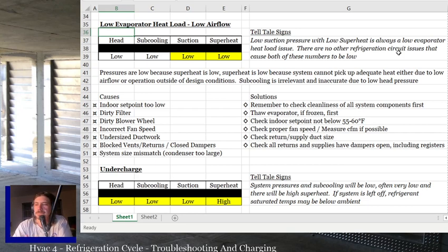Now, I will say this, though. My experience has been, and this isn't all the time, but it's most of the time, if you've got low evaporator heat load because of a dirty filter, or a damper's closed that shouldn't be closed, or whatever the case may be, and it's frozen up when you get there, you thaw it out and throw a new filter in. Don't necessarily call it good, because my experience has been that if the system actually freezes up into an entire block of ice, it's usually a combination of low airflow and probably a slight to reasonable undercharge.